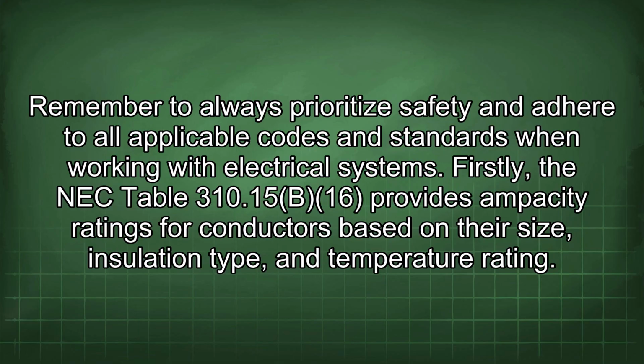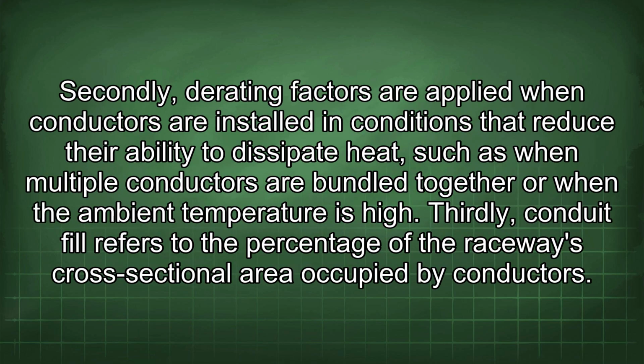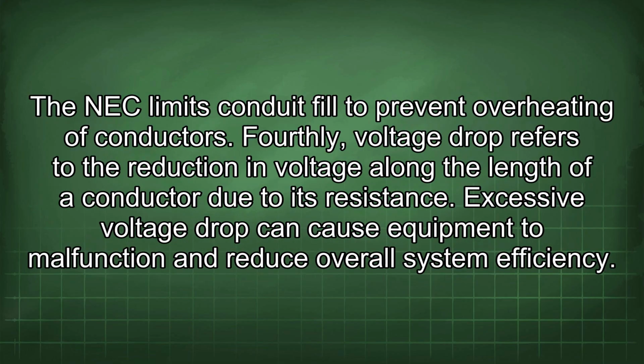Firstly, the NEC Table 310.15(B)(16) provides ampacity ratings for conductors based on their size, insulation type, and temperature rating. Secondly, derating factors are applied when conductors are installed in conditions that reduce their ability to dissipate heat, such as when multiple conductors are bundled together or when the ambient temperature is high. Thirdly, conduit fill refers to the percentage of the raceway's cross-sectional area occupied by conductors. The NEC limits conduit fill to prevent overheating of conductors.